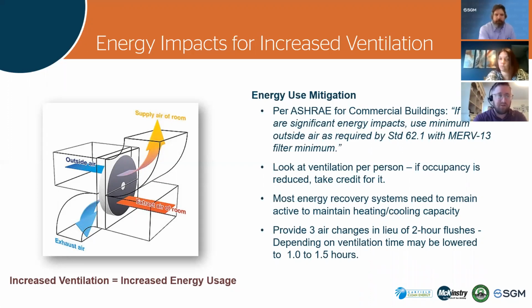Additionally, with most energy recovery systems, the systems downstream of those are designed to take advantage of them. And in a lot of cases, we can't turn those off. So a lot of times we're recommending we maintain those and keep them active and just assess the sealing and make sure they're not leaking. Additionally, that 2-hour flush, you can look at it in terms of air changes and target 3 air changes. And for spaces with increased outside air, we've been able to lower that time a little bit, which is going to help your energy use a little bit.